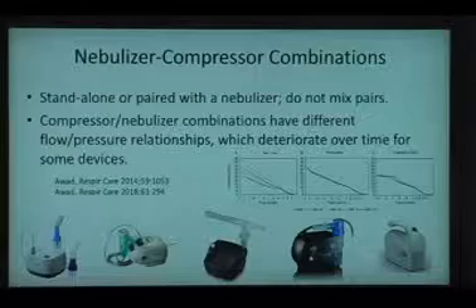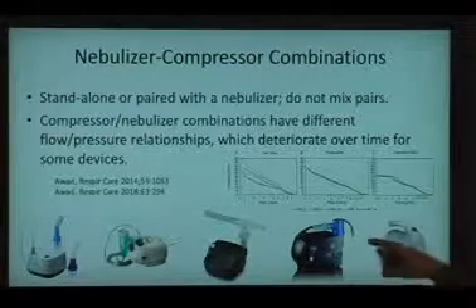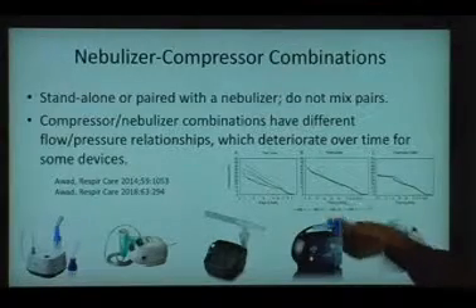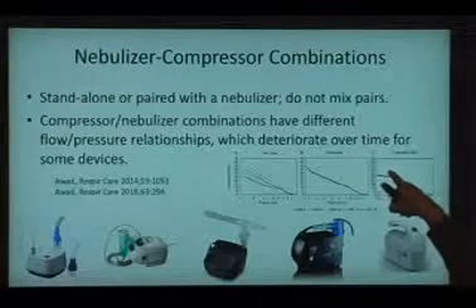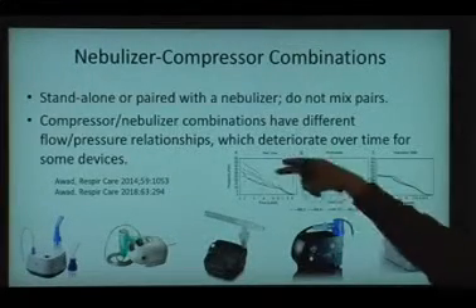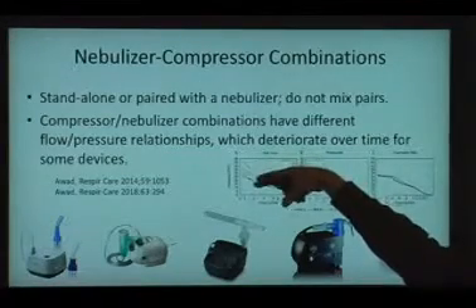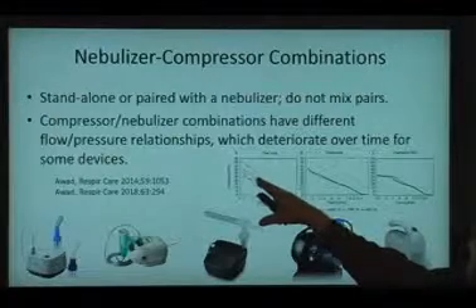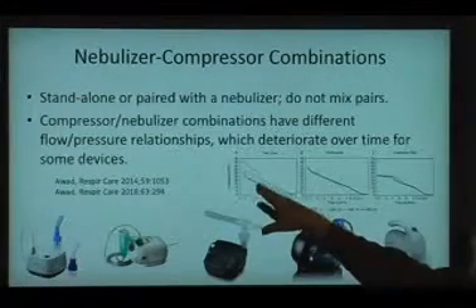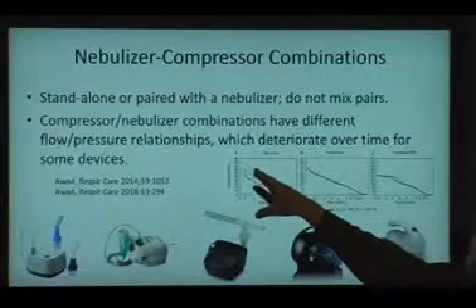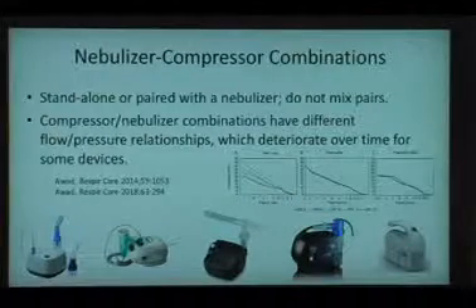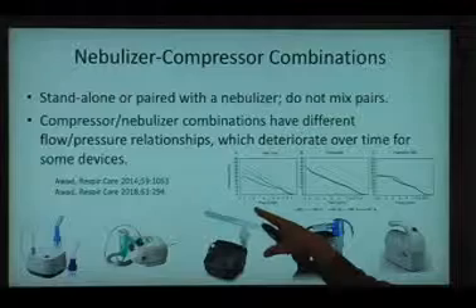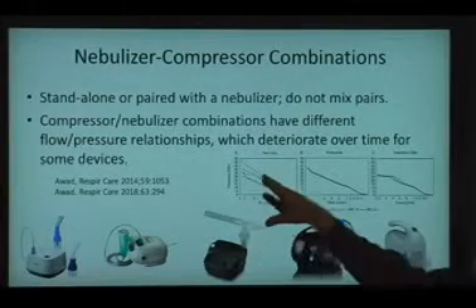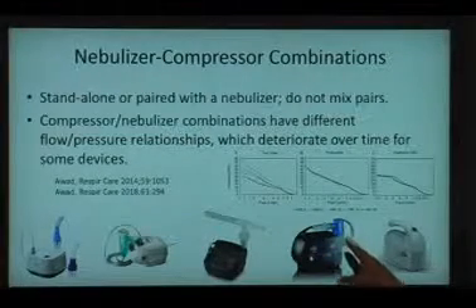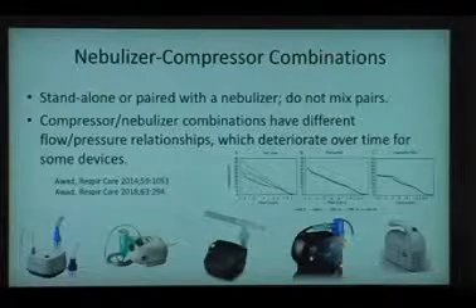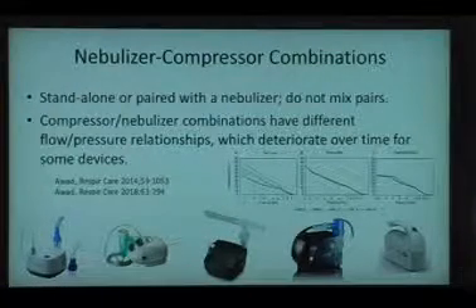Also, some compressors deteriorate in their function over time. The lines here do not overlap, and they studied, I forget how many different compressors. This is the performance of the nebulizer at week 0, week 6, week 12, week 18, week 24. Over 24 weeks, roughly half a year, the performance of this compressor nebulizer combination deteriorated quite a lot. So that might not be a good thing.